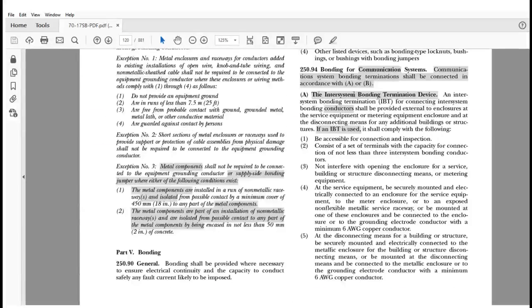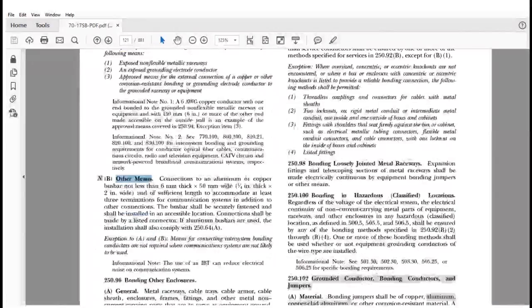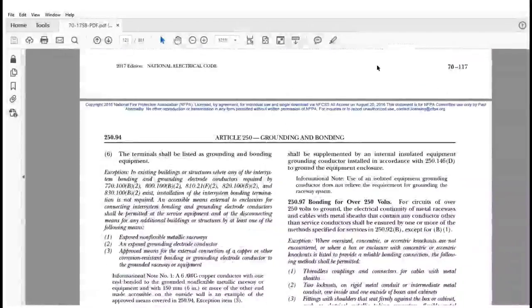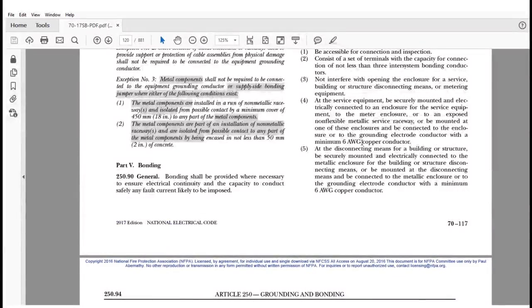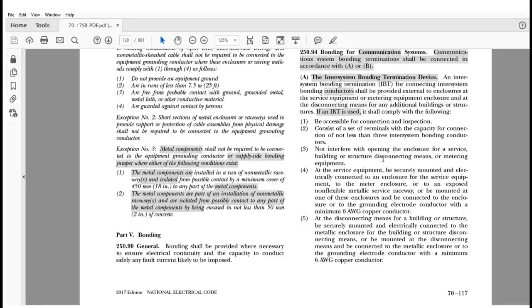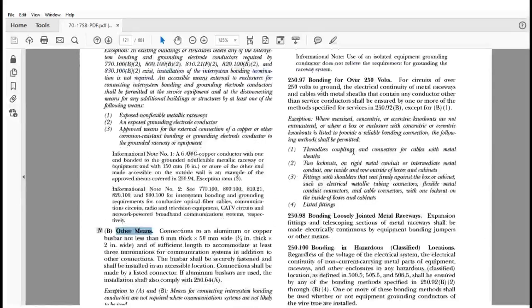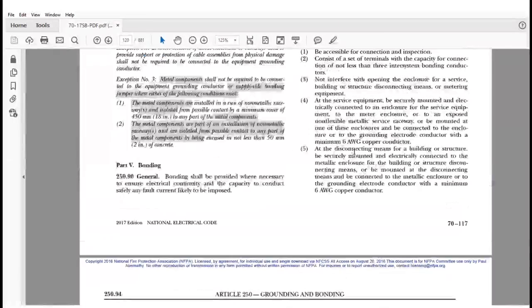You don't want to use this listed device that's listed for inter-system bonding terminals only. But you want to put another device there, and you want to make these connections there. You want to make all of these connections for the CATV, cable, whatever. You want to do that? That's fine. You can do that. I would encourage against it because of noise and interference between the systems.